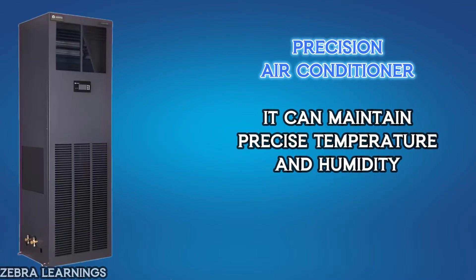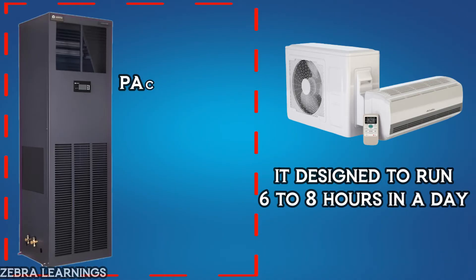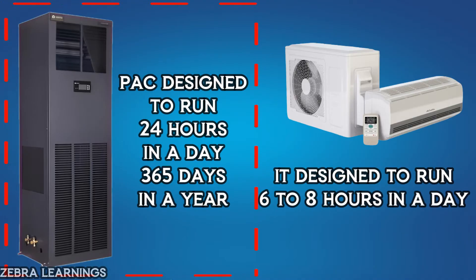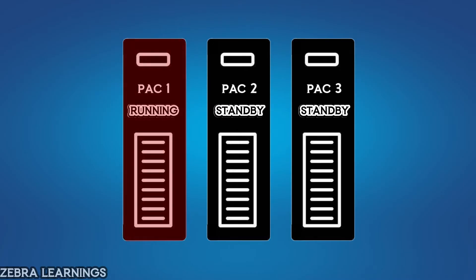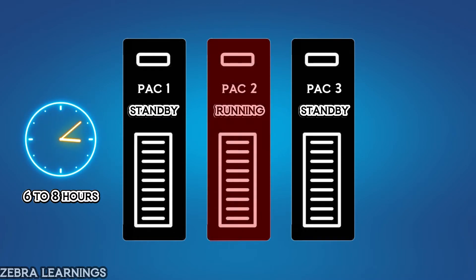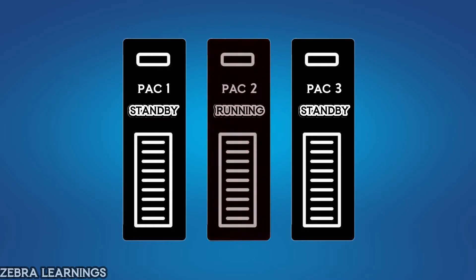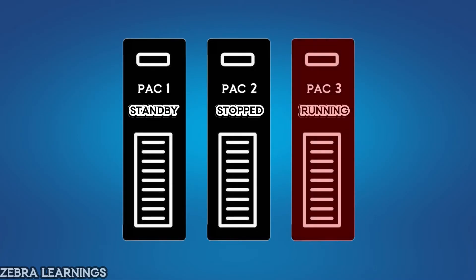But a precision air conditioner can maintain much more precise temperature and humidity. And the normal AC we use runs for about 6 to 8 hours a day. However, PACs are designed to run 24 hours a day, 365 days a year. In most cases, at least 3 PACs are used in a single location. Every 6 to 8 hours, each PAC automatically switches over and takes over the operation. If there is a problem with one PAC, the next PAC automatically starts running, ensuring that the unit remains in continuous operation.